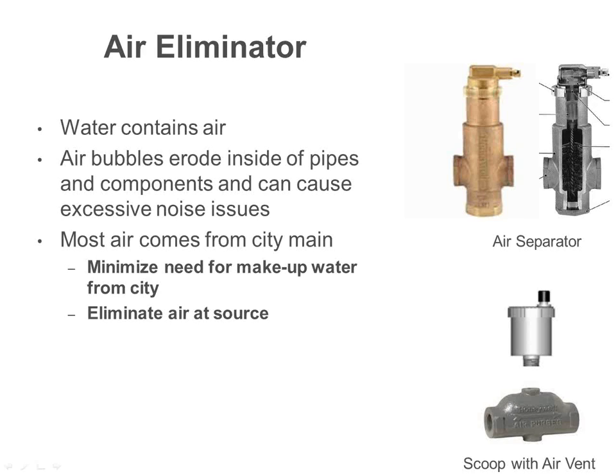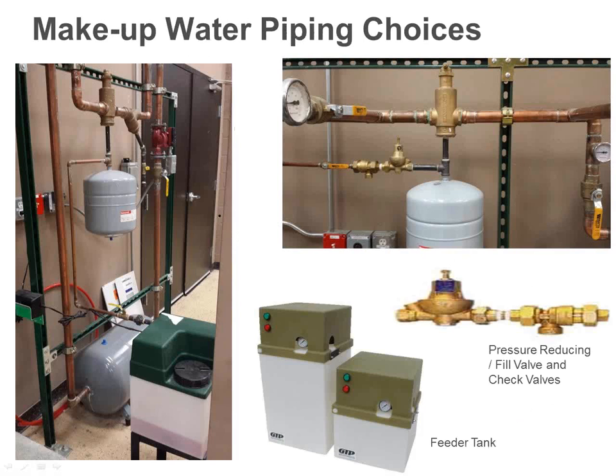Okay, the bottom one is a scoop with an air vent. That was nothing more than a piece of pipe with a bulge in it. And basically on top of that we put a $5 air vent. As soon as the $5 air vent clogged up with crap, everybody shut it off. Now your whole air elimination system was no good because you had none. Once you close that vent, it's over. So most of the air comes from the city main. We want to minimize that air getting in the system. So on our next slide, I think we should talk about proper piping system and where to pipe it in. Okay, if you look at the top picture and the left picture, the left picture is probably the easier one to see. You'll see by the red dot, there's the actual air eliminator right in the middle.